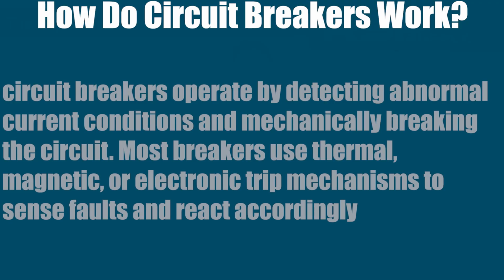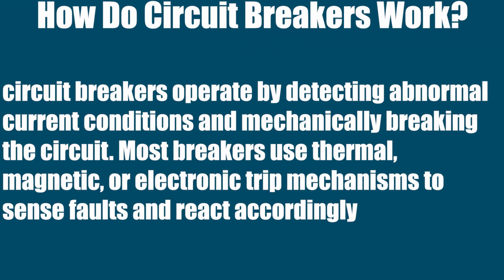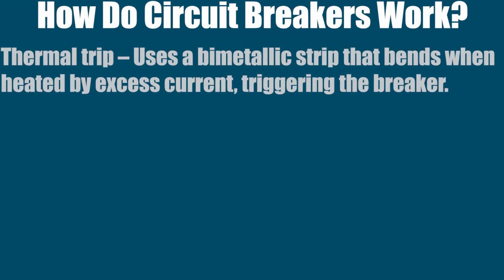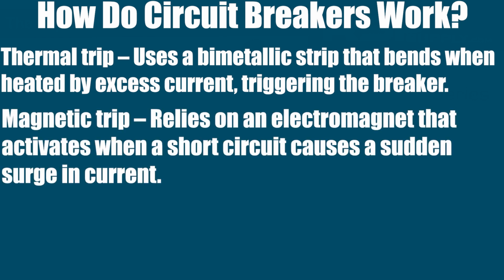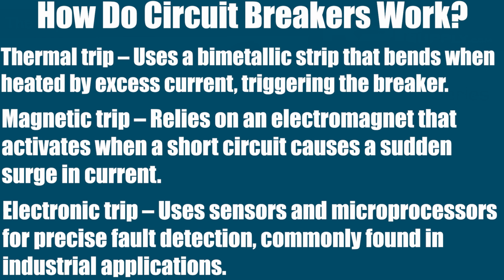At a deeper level, circuit breakers operate by detecting abnormal current conditions, and then they mechanically break the circuit. Most breakers use thermal or magnetic or electronic trip mechanisms to sense faults and react accordingly. For example, a thermal trip uses a bimetallic strip that bends when heated by excess current. This triggers the breaker. A magnetic trip relies on an electromagnet that activates when a short circuit causes a sudden surge in current. An electronic trip uses sensors and microprocessors for more precise fault detection, and it's commonly found in industrial applications.